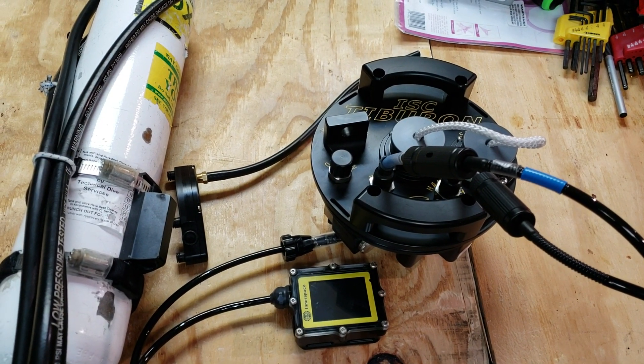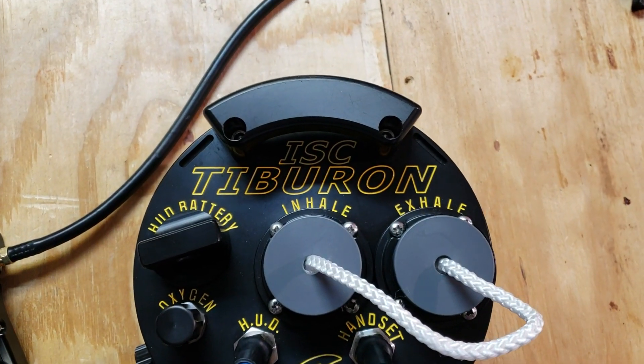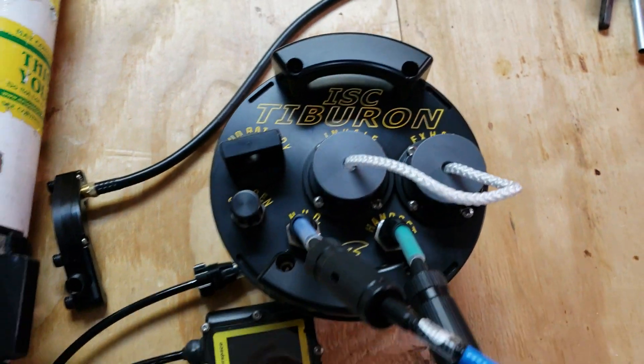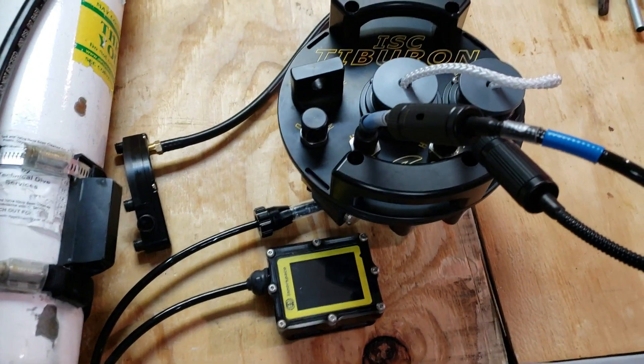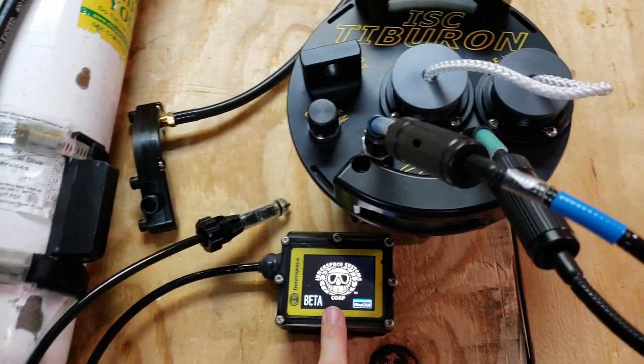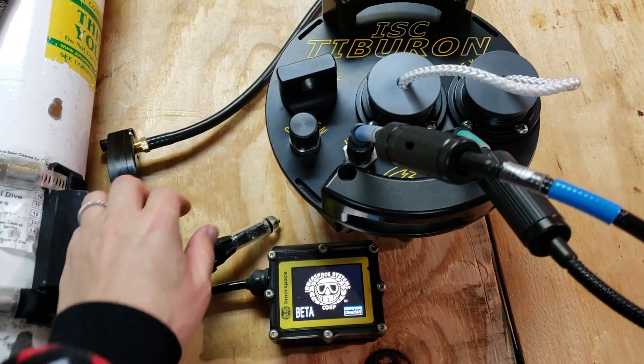Hey everyone! This video is going to be the calibration for the new Tiburon rebreather head. Specifically, this is going to be an O2 calibration for the HUD only, because your Petrel can calibrate to air. So I'm going to do an air point calibration on the Petrel and an O2 calibration on the HUD.